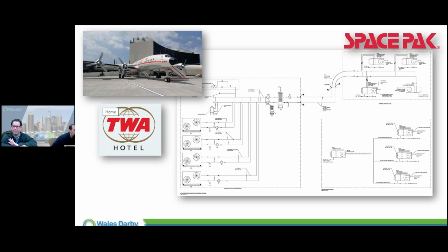I'm just going to tap into something about the choice of piping and glycol, and then sizing and selection. PEX is a very popular choice of material, SDR9. The ID of half-inch PEX is not the same as the ID of half-inch copper or steel. Know what that does for your pump selection, and then you add glycol.